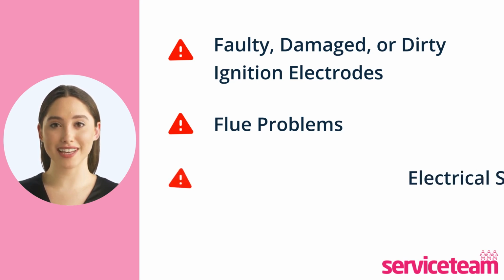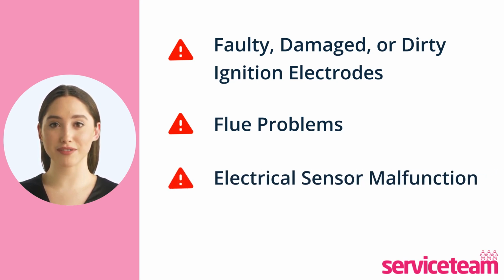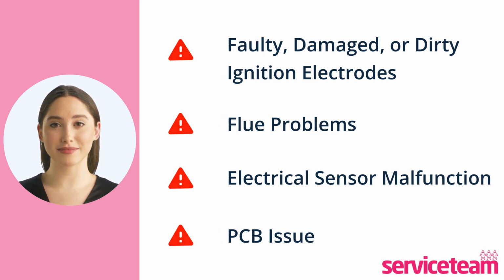The next cause is electrical sensor malfunction. This means, when the boiler flame sensor malfunctions, it can give wrong readings and trigger the F7 code. Finally, if your boiler's printed circuit board or PCB is damaged or faulty, it can mess with signals from the flame sensor. Usually, the PCB is essential for controlling operations.